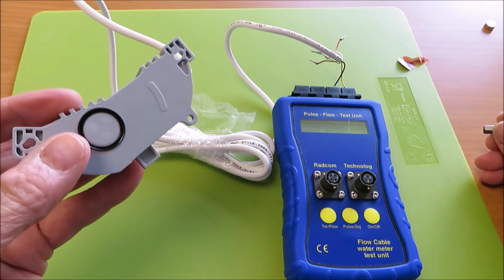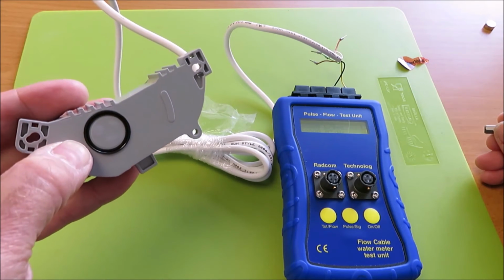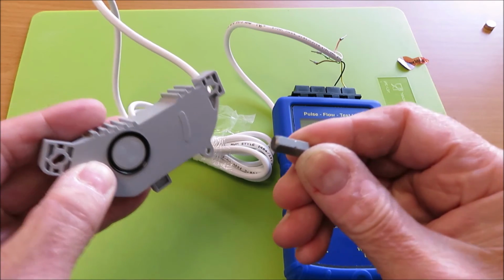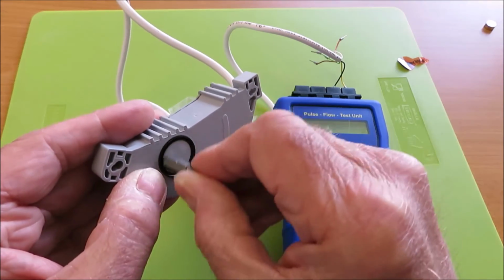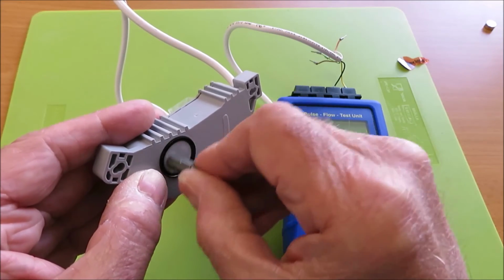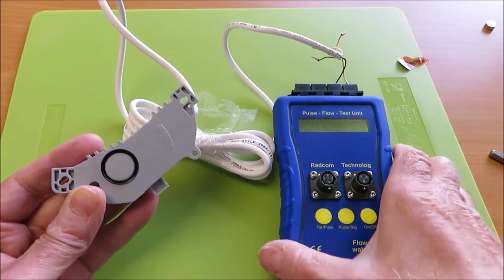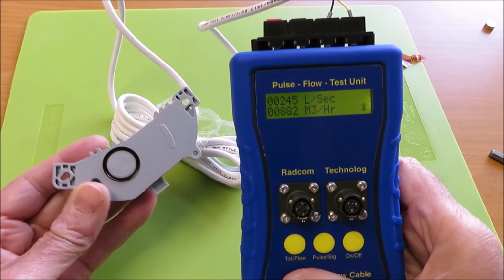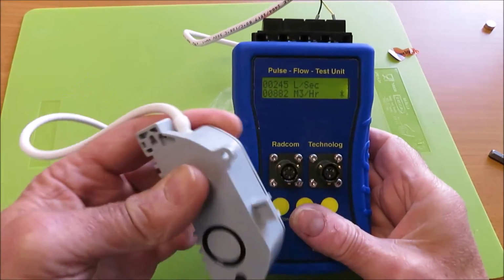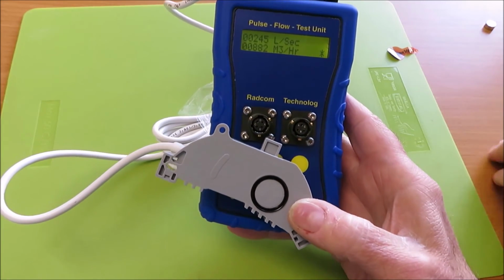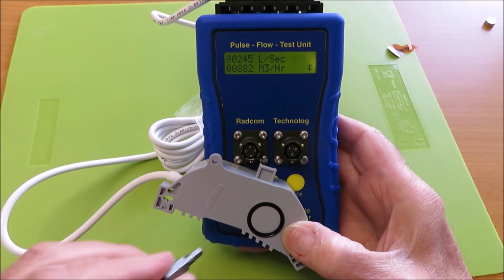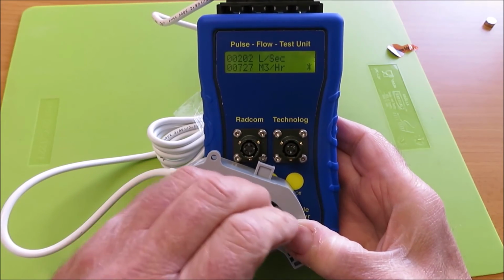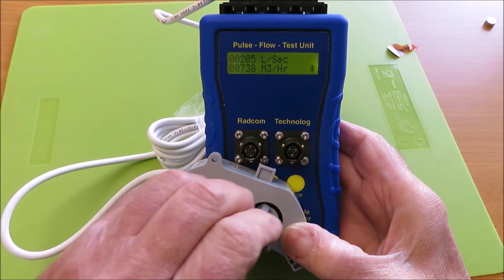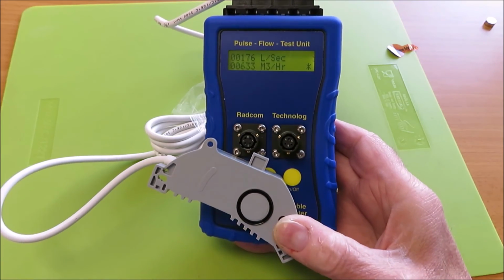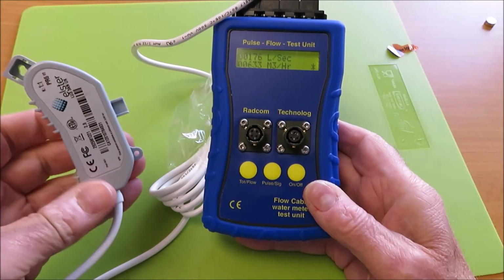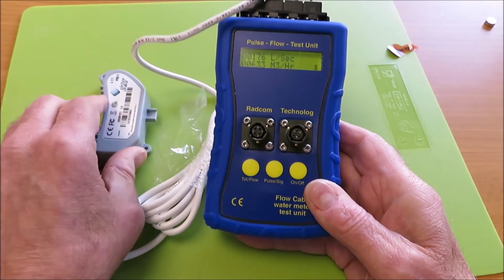And the way to test one of these is I'm going to, using my thumb, hold the little black button down, so that's depressed, and then I'm going to get the little screwdriver bit, and in a circular motion I'm going to go around like that in one particular direction. And then if this is operating, you'll get a flow rate. And as you can see, there's the flow rate. I'll try and do that now using my left hand so that you can see the display without knocking the camera. I'm pressing the button in again, I'm going round in a circle. As you can see, we're getting a flow rate. So that confirms that actually this particular sensor is operating correctly, so it will record a flow rate, so that's not faulty in any way.